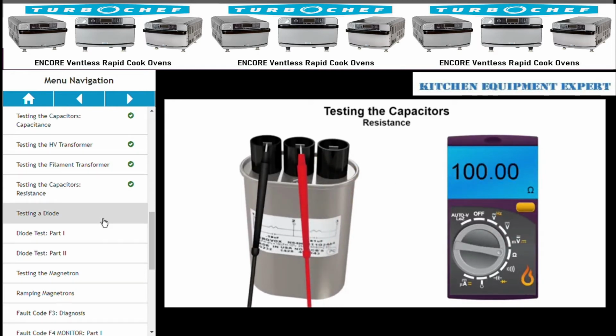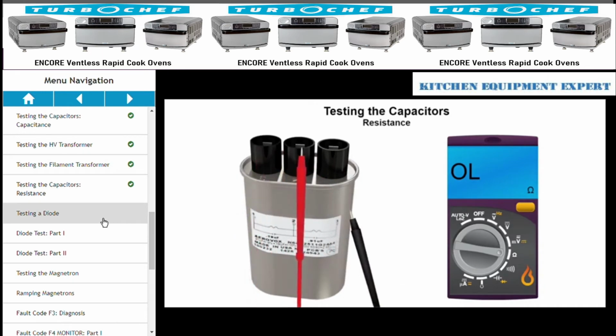You should get a momentary reading, then a slow return to an open or infinite resistance reading. Reverse the leads and you should get the same results. If you see a reading that doesn't change or an infinite reading, when you first connect your meter, you have a bad capacitor. Check each terminal to the case for shorts.